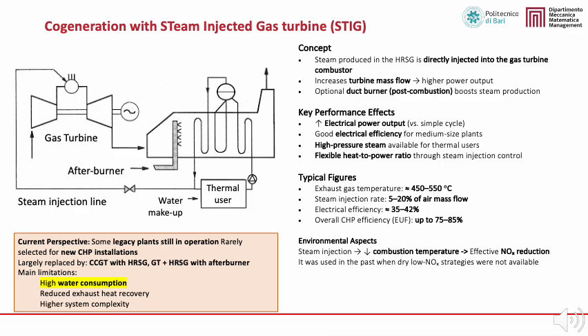In terms of performance, STIG systems offer good electrical efficiency compared to simple cycle gas turbines and allow the production of high pressure steam. An important feature is the flexibility of the thermal to electric ratio, which can be controlled by regulating the steam injection rate. Typical operating values include exhaust gas temperatures between 450 and 550 degrees Celsius, steam injection rates of about 5 to 20% of the compressor air flow, electrical efficiencies in the range of 35 to 42%, and overall cogeneration efficiencies up to about 85%. From an environmental standpoint, steam injection lowers combustion temperature and is effective in reducing NOx emissions, often in combination with additional emission control systems.